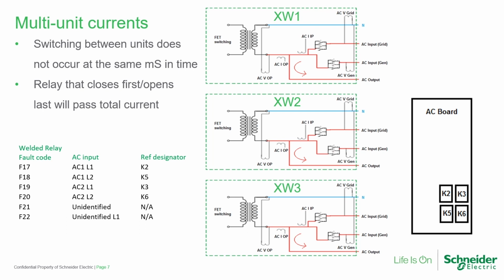A loop from input to output usually occurs when the customer fails to have a bypass interlock in place or just a miswire. Sometimes a welded relay can be unstuck by tapping on the plastic cover with the back of a screwdriver handle. Historically, when welded relay faults occurred in the past, they were covered under warranty in many cases.